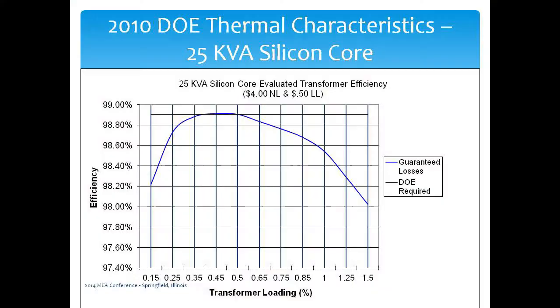So there were some things that people were doing, and all of a sudden their newer DOE designs were significantly less in weight and cost. In a lot of cases, yes, it ran at 50% load and it was right on that DOE efficiency where it should be, but within that range, that area under the curve was very small. And so we see units starting to burn up where they hadn't burned up before, and they shouldn't have burned up, because they were trying to hold it to a narrow bandwidth. But when you look at the area under the curve, that's the key thing.